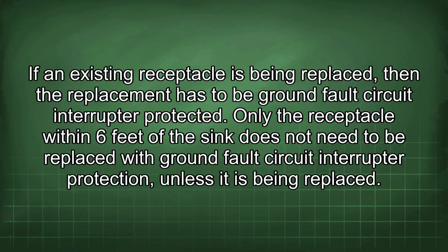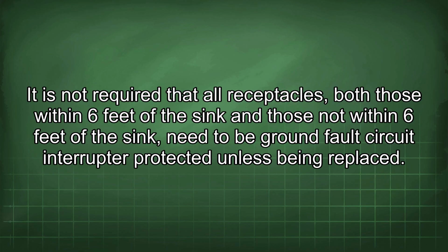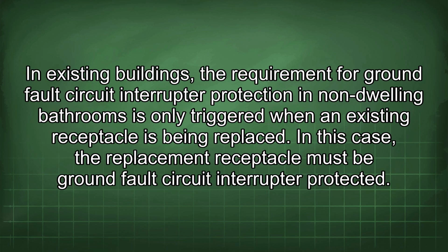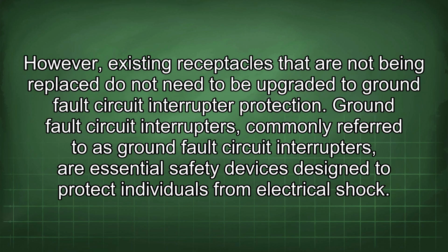Only the receptacle within 6 feet of the sink does not need to be replaced with ground fault circuit interrupter protection unless it is being replaced. It is not required that all receptacles, both those within 6 feet of the sink and those not within 6 feet of the sink, need to be ground fault circuit interrupter protected unless being replaced. In existing buildings, the requirement for ground fault circuit interrupter protection in non-dwelling bathrooms is only triggered when an existing receptacle is being replaced. In this case, the replacement receptacle must be ground fault circuit interrupter protected. However, existing receptacles that are not being replaced do not need to be upgraded to ground fault circuit interrupter protection.